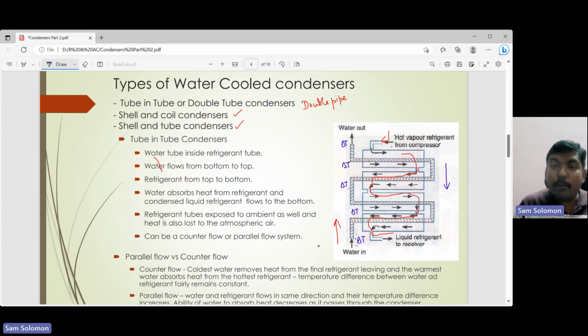Whereas if it is going to be a parallel flow, where you have water entering from top to bottom and you have the refrigerant entering from top to bottom, you can see that in this case the temperature is less at the entry, whereas here you have a higher temperature. When it goes out, here it has the higher temperature, and here it has a relatively lower temperature. The temperature difference is huge. So when the temperature difference is huge, that is going to affect the heat carrying capacity of water. So that is not going to result in an efficient heat removal. So it is always preferred to have a counterflow heat exchanger.